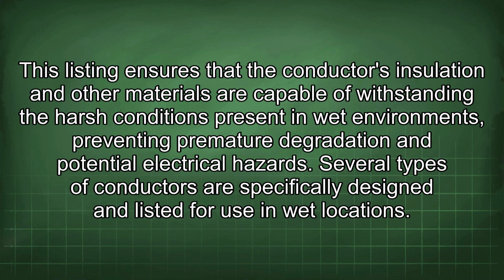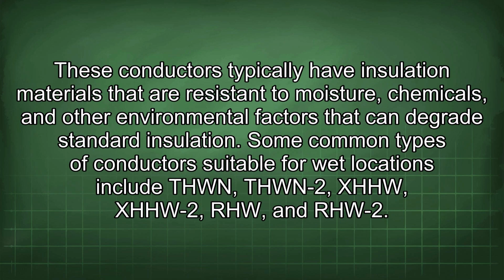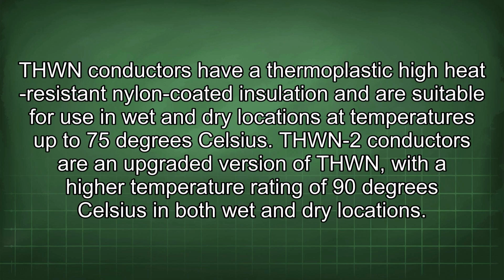Several types of conductors are specifically designed and listed for use in wet locations. These conductors typically have insulation materials that are resistant to moisture, chemicals, and other environmental factors that can degrade standard insulation. Some common types of conductors suitable for wet locations include THWN, THWN-2, XHHW, XHHW-2, RHW, and RHW-2. THWN conductors have a thermoplastic high heat resistant nylon coated insulation and are suitable for use in wet and dry locations at temperatures up to 75 degrees Celsius.